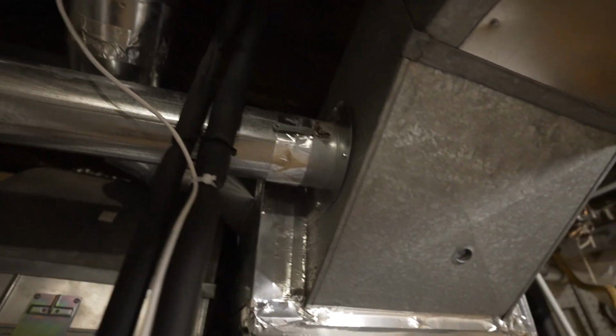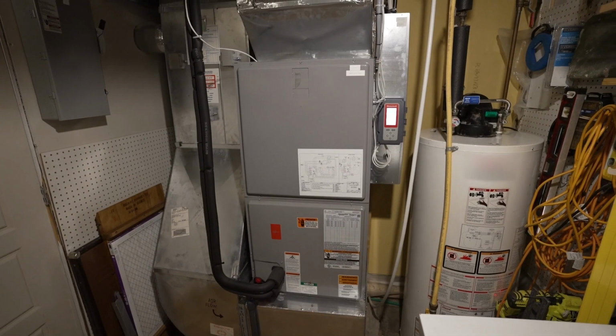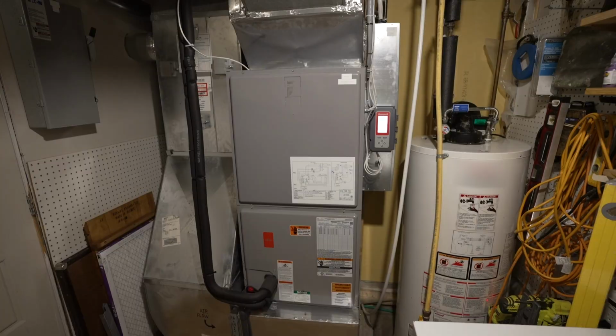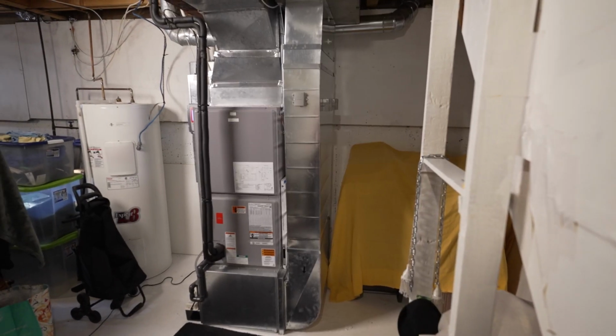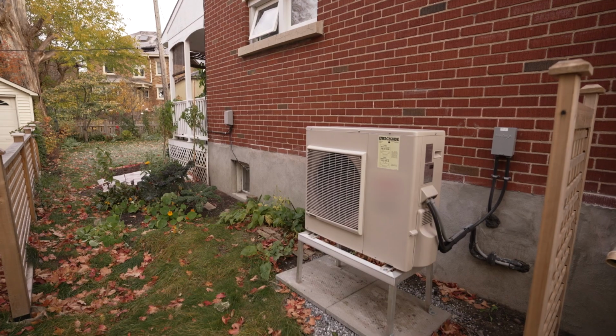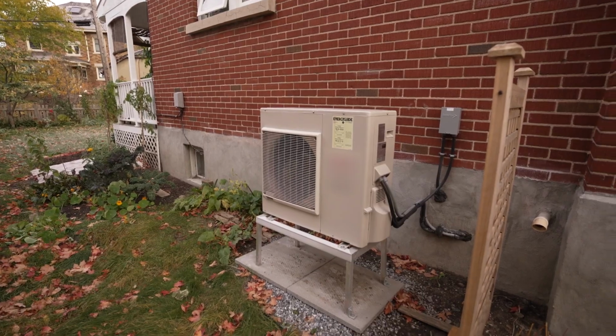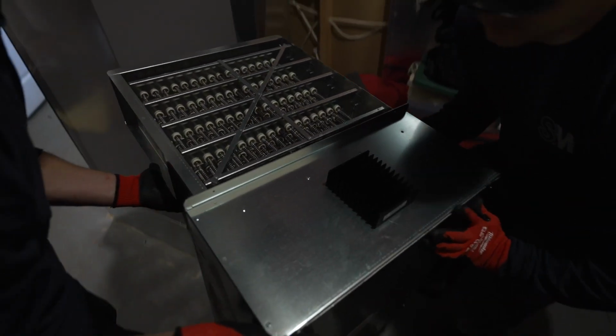compared to conventional furnaces. Next, we assess the physical dimensions, space, and clearance for the outside unit, room in the furnace room for the air handler. These are key factors to determine if the home is a good candidate. Secondary considerations include, do you need backup heat? We've seen many jobs where the heat pump is grossly oversized for the home's heating requirements.